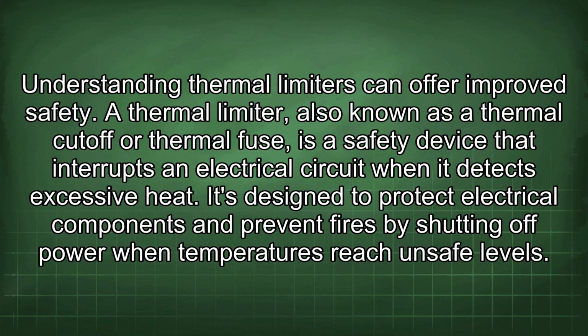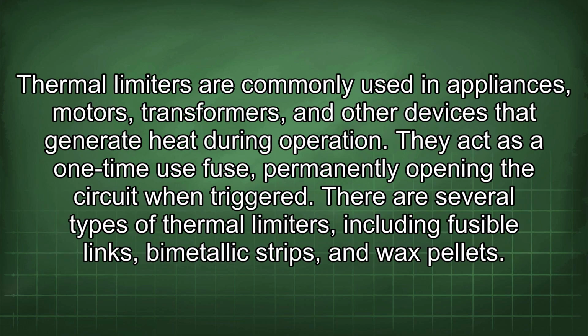A thermal limiter, also known as a thermal cutoff or thermal fuse, is a safety device that interrupts an electrical circuit when it detects excessive heat. It's designed to protect electrical components and prevent fires by shutting off power when temperatures reach unsafe levels. Thermal limiters are commonly used in appliances, motors, transformers, and other devices that generate heat during operation. They act as a one-time use fuse, permanently opening the circuit when triggered.